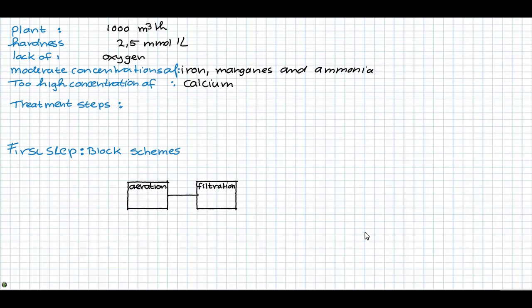And a too high content of calcium. To treat this water, we need at least one aeration and filtration step and a softening step. The latter can be done by nanofiltration, ion exchange or pellet softening.